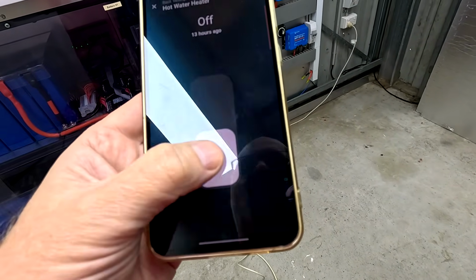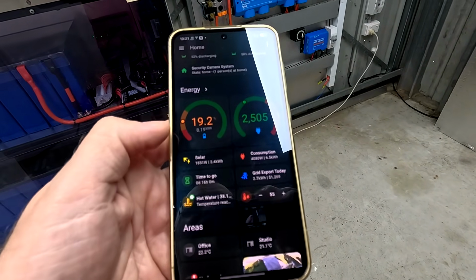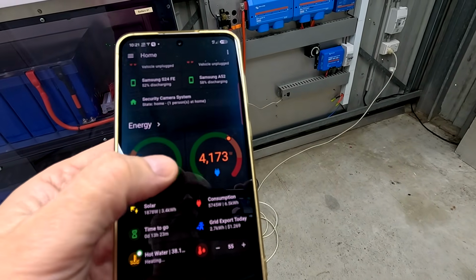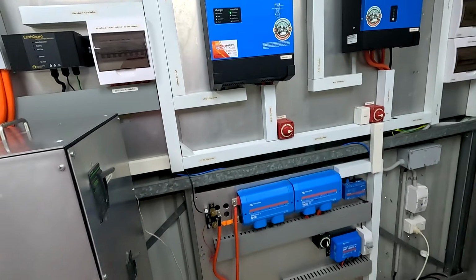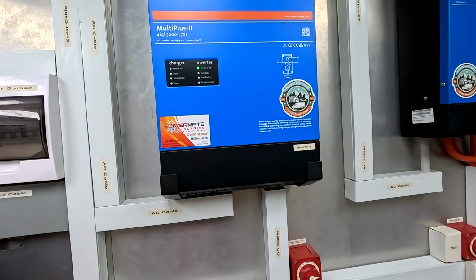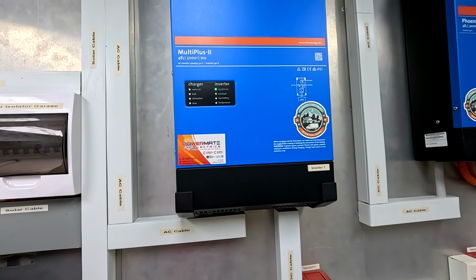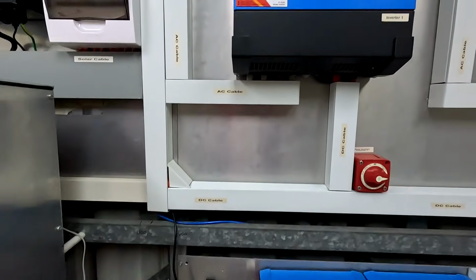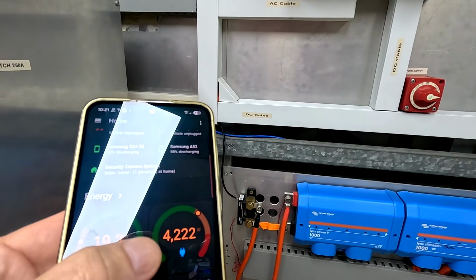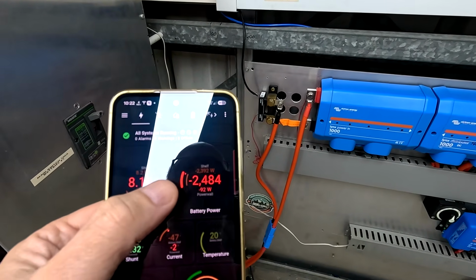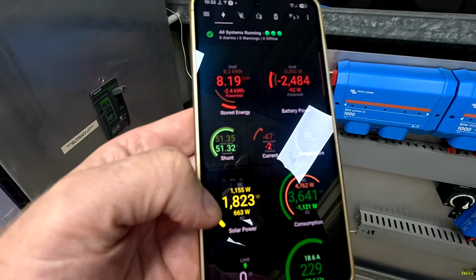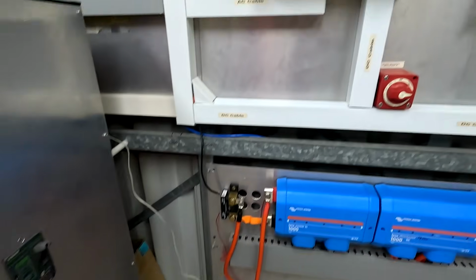Let me actually turn on the hot water here as well, so that's another 1.5 kilowatt, and we should be now over 4.1 kilowatts here for the Multiplus. Because it's a bit colder here inside the battery room, it doesn't show any overload or something, so we're pulling over 4.2 kilowatts now from the Multiplus. That means around 2.4 kilowatts coming from the battery and 1.8 from the solar directly.